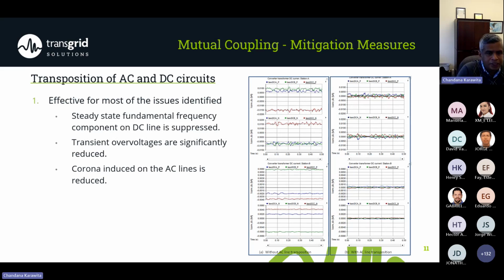And the other option is transposition. What we observed is that if we can transpose AC lines mainly, and in some cases DC circuits as well, this is one of the most effective solutions for most of these issues that we identified. So if you can transpose the AC line, we can easily get rid of the steady state fundamental frequency components on the DC lines, the transient over voltages are significantly reduced, and you can reduce the corona effect as well.